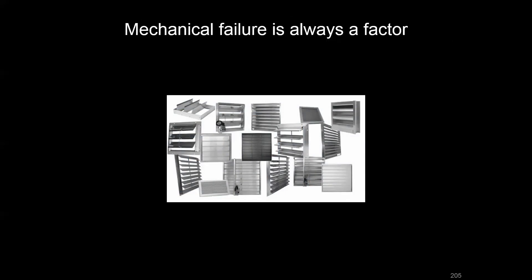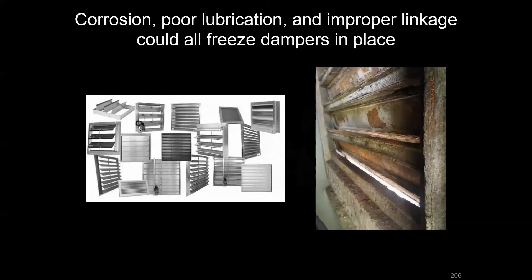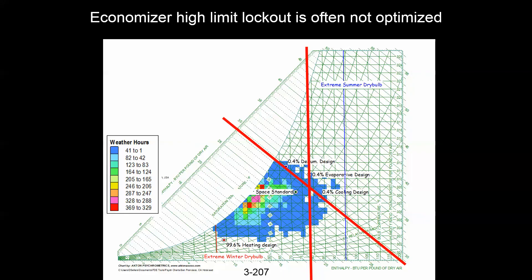Even with a well-working control system, mechanical devices are subject to failure. In marine climates or high humidity environments, depending on duct and damper construction and lubrication frequency, dampers may become stuck or frozen — commanded to a certain position by the automation system but physically stuck where they were — which creates a whole range of problems.